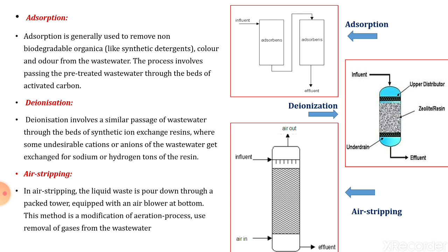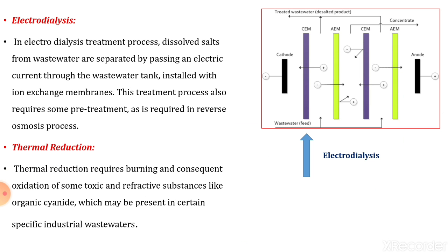In air stripping, the liquid waste is poured down through a packed tower equipped with an air blower at the bottom. This method is a modification of the aeration process and is used for removal of gases from wastewater. The influent comes into contact with air blown from the bottom while the influent enters from the top. Undesirable gases present in the wastewater are released and the clear effluent is taken out from the bottom.